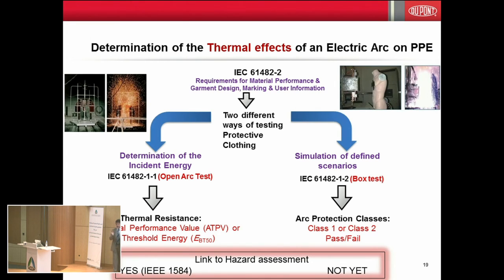Previously we analyzed an electrical system and came up with an energy level that could occur in case of an arc - in the example, it was 7.1 calories. Then you know you need protective equipment rated at least 7.1, and the ATPV or EBT gives you that relation. So this methodology has the advantage of linking the fabric characterization results directly to the hazard assessment.